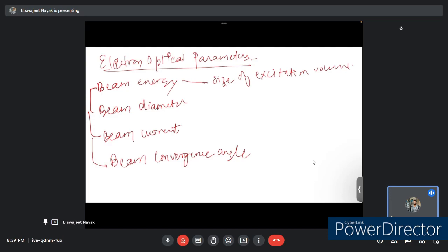In many microscopes it is possible to do so by decelerating the electron beam, which decreases the beam energy just before the electron emerges from the objective lens. Similarly, we can increase the energy of the electron. The term used to describe the electron beam energy at the point of impact on the sample surface is called landing energy.